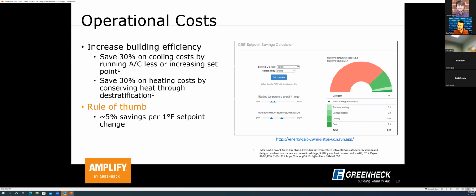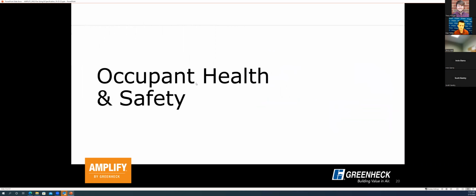You're essentially wasting a lot of the heat you paid for. By pushing that warm air back down to floor level and reducing the temperature delta from floor to ceiling, we're able to conserve more heat and reduce the amount of heating needed, just by recapturing already heated air. General rule of thumb: there's about a 5% energy savings for every 1 degree you're able to offset with an HVLS fan. So if you can offset a 5, 10, or 15 degree temperature delta from floor to ceiling, there are significant savings achievable, in addition to the rest of your HVAC system.